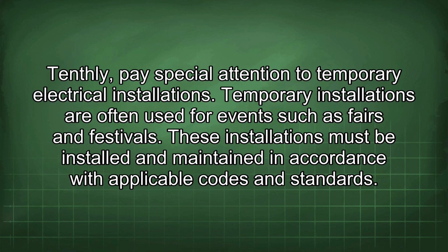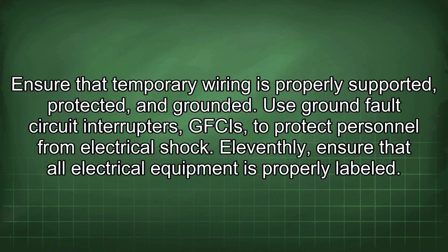Tenthly, pay special attention to temporary electrical installations. Temporary installations are often used for events such as fairs and festivals. These installations must be installed and maintained in accordance with applicable codes and standards. Ensure that temporary wiring is properly supported, protected, and grounded. Use ground fault circuit interrupters, GFCIs, to protect personnel from electrical shock.